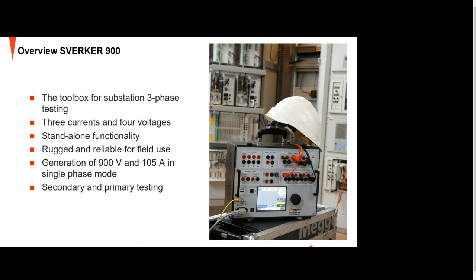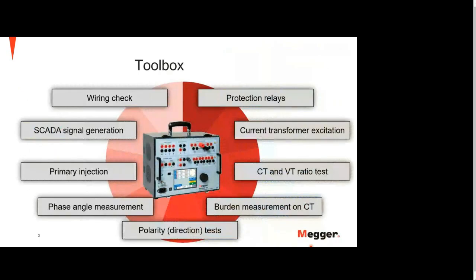So SVERKER 900 is a complete toolbox, as we said, for testing the substation. You can use it for doing wiring checks. Also, you can use it for testing the signals up to the SCADA, the dispatch center, checking from relays and meters up to the SCADA, to simulate the power, for example, or energy for an energy meter. It's also possible to do primary injection.